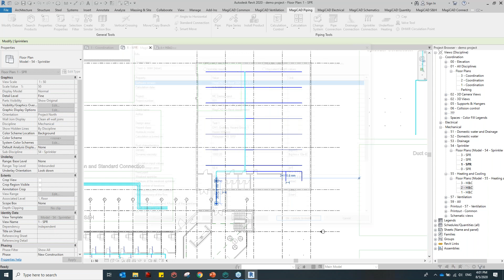Now my sprinkler calculation report is ready. Here you can see what standards I have used, my project name, my design area, the hazard class, and the hydraulic method I'm using, which is the Hazen-Williams formula. The calculation is based on Malaysian standard MS1910, showing the design density, viscosity, and the design area in meter square along with the feed point number.